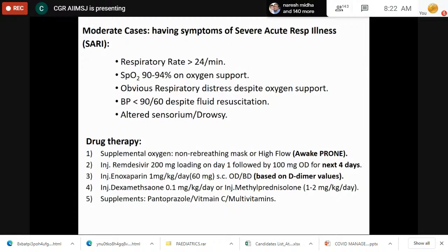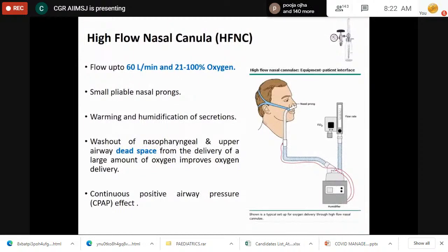Now, with the advent of COVID infection, a new device, the high flow nasal oxygen or high flow nasal cannula, has come into action. It was known from the last 10 years, but it was not in so much use. But with COVID, there is rampant use of high flow nasal cannula. This is a device in which there is a humidifier, there is a compressor in the chamber, and you attach the device to an oxygen source. The advantage is that you get a very high flow. Normally, this is the conventional flow meter in which you have a flow regulator, you can see the flows, and you have a chamber to humidify the air. The limitation of the device is that the maximum flow we can give is only 15 liters per minute.